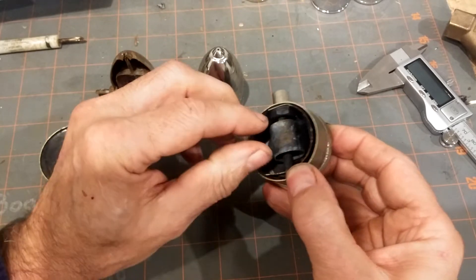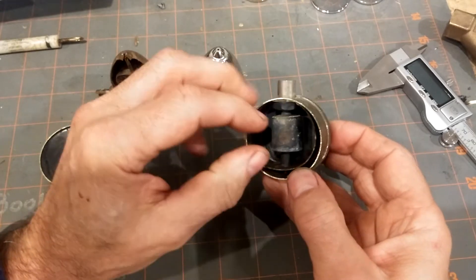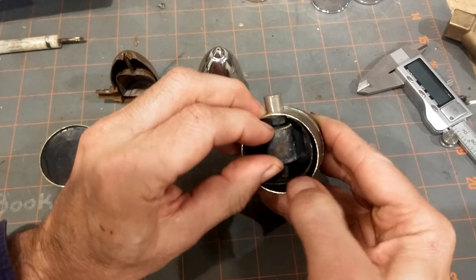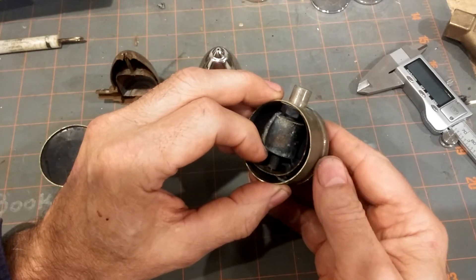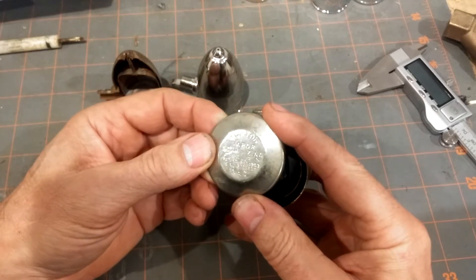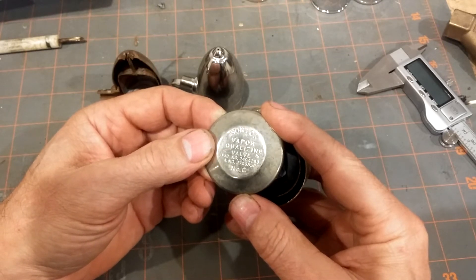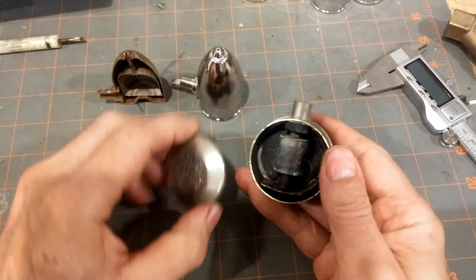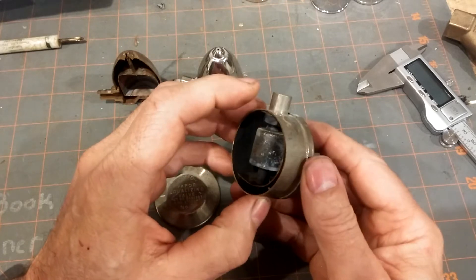This chamber is designed to catch air. If the vent fills up with water, it will also drive the seat up, reducing the amount of water coming out of the vent. There are a couple of patent numbers on this: 2494293 and 2709550. A superficial examination of them has to deal with the details of the bimetallic strip in question.